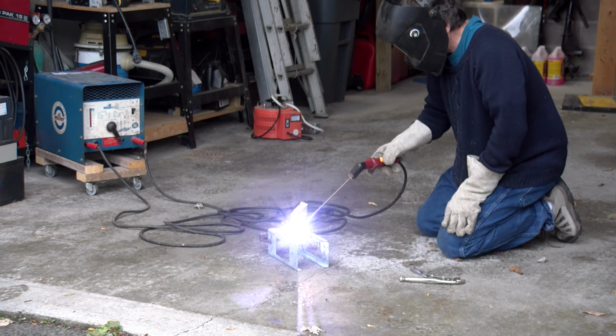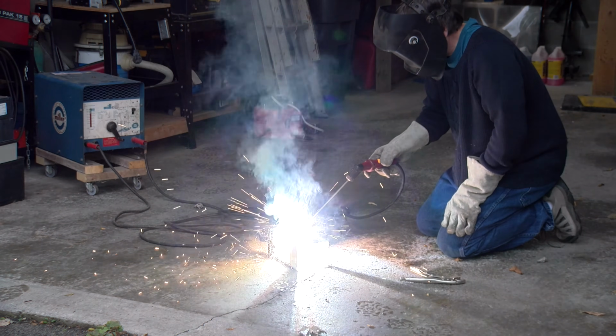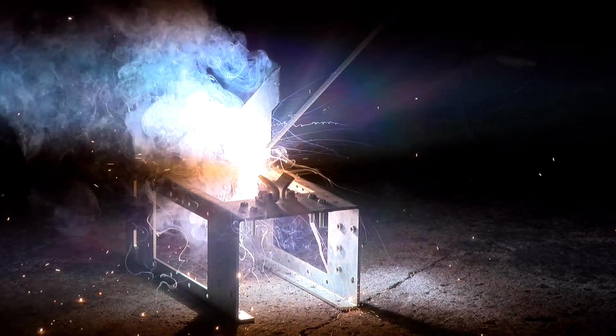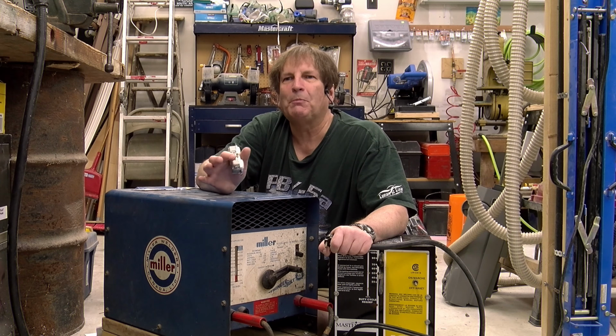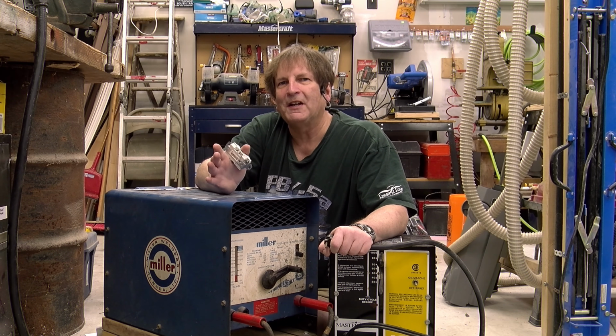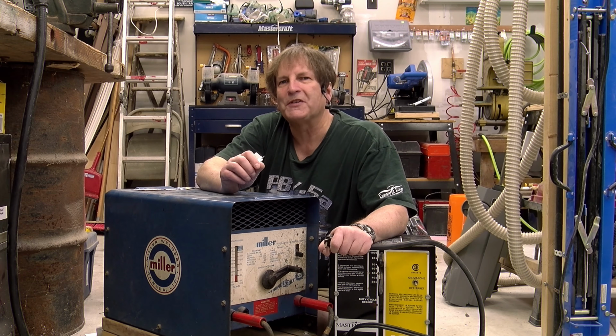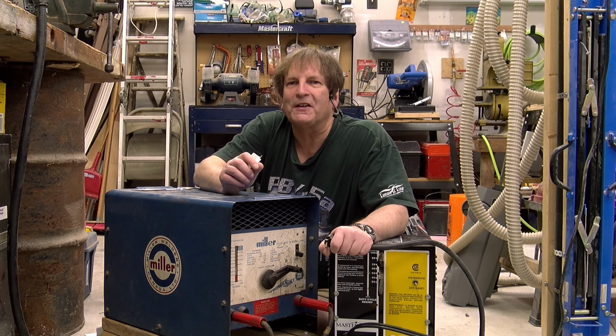To generate the somewhat crude constant current that's needed for a welder, they use nothing but a giant transformer. But that transformer is not quite the same as a typical power transformer. It actually has a leaky magnetic circuit that allows one to shunt some of the magnetic field in the core between the primary and the secondary.